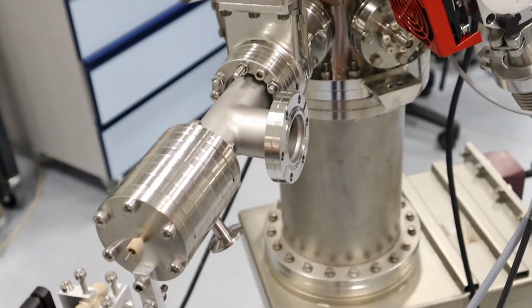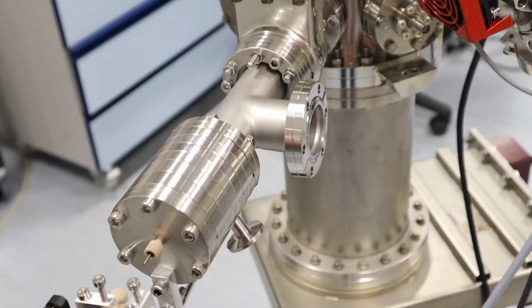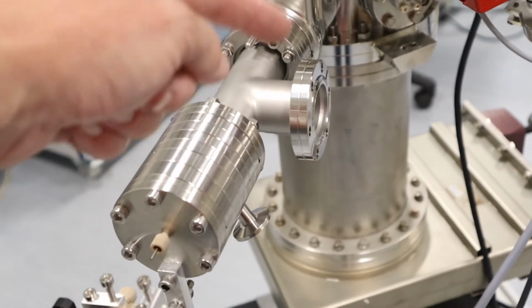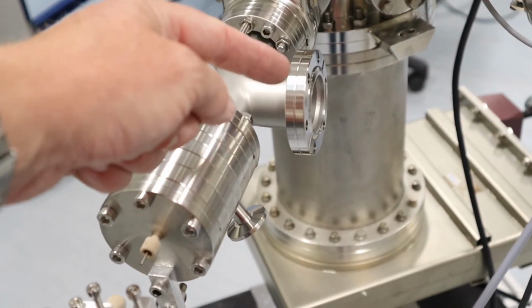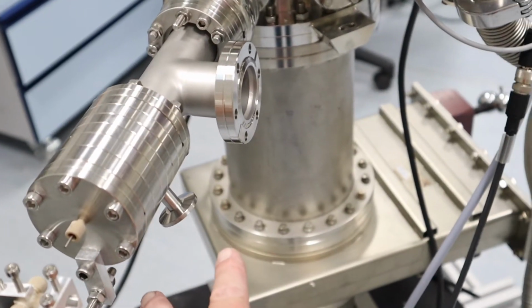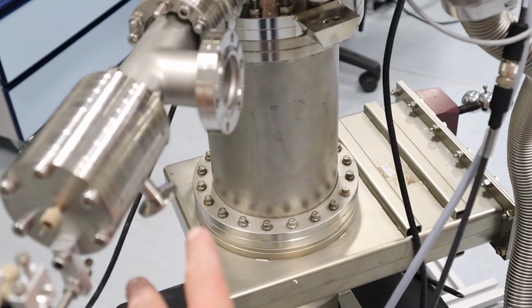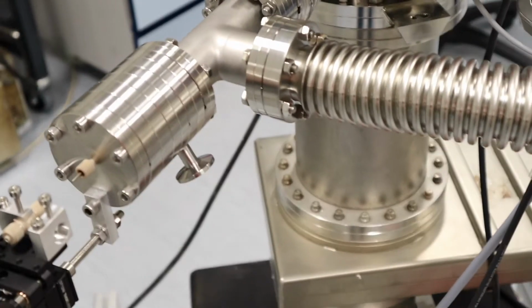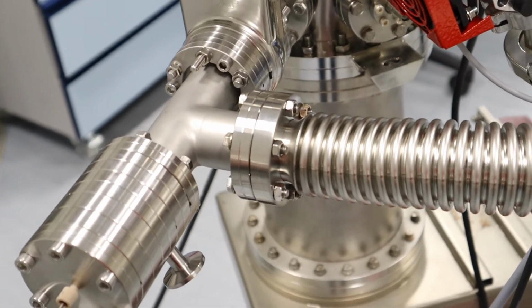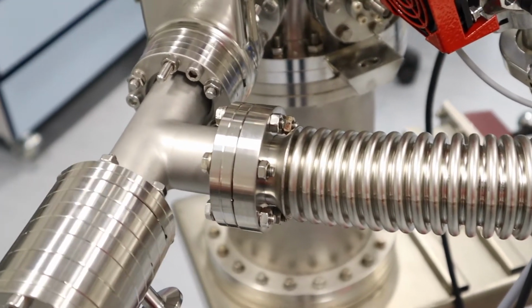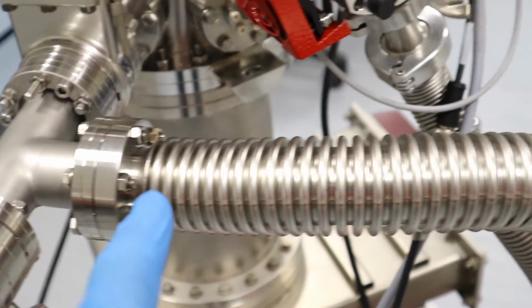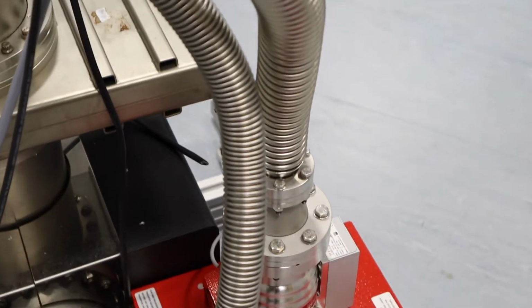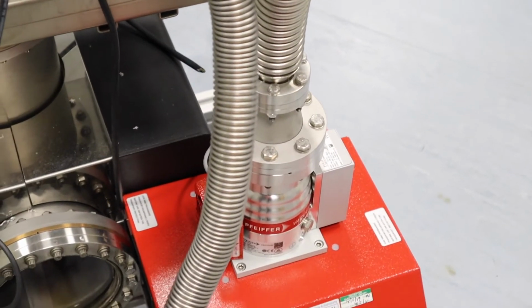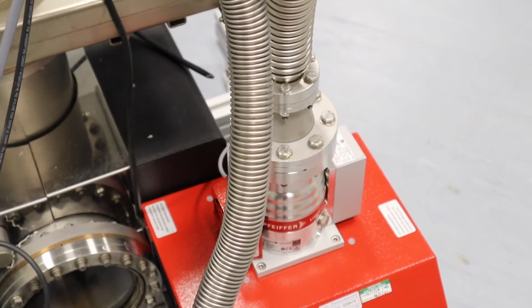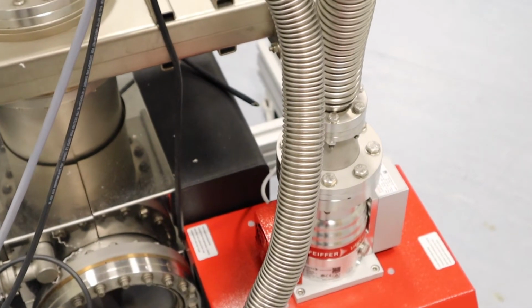So I'm going to go ahead and attach the pumps. The first thing I'm going to do is attach the turbo molecular pump stage first, and then I'll attach the scroll pumps to stages 1 and 2. So for the purposes of this demonstration and test, I've attached the turbo stage using the bellows down to a HiCube, which is essentially a HiPace 80 with an integrated diaphragm pump.